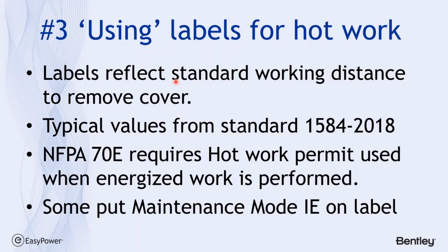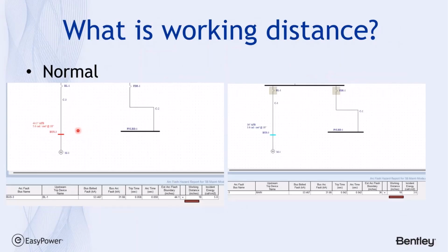But to do hot work, NFPA 70E requires that a hot work permit should be used, and that's where you do a working distance calculation for the task at hand. Now, this comes to a point ahead in the discussion when some people want to use maintenance mode incident energy on the label. I don't think that's a good idea either. I say that because if my method says I'm going to compare normal operations to incident energy based upon maintenance mode, and I'm going to put them both on a label, and I look at the results that I'm depending on, the working distance in both cases is 18 inches. But the task that I'm trying to do under maintenance mode may be something much closer than 18 inches.